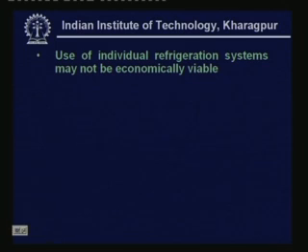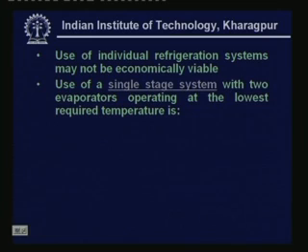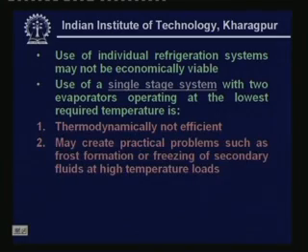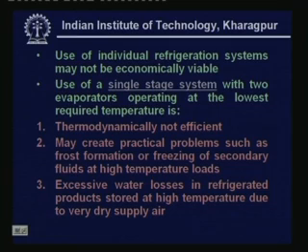Use of individual refrigeration systems may not be economically viable. And use of a single-stage system with two evaporators operating at the lowest required temperature is thermodynamically not efficient. It may create practical problems such as frost formation or freezing of secondary fluids at high-temperature loads, and excessive water losses in refrigerated products stored at high temperature due to very dry supply air.